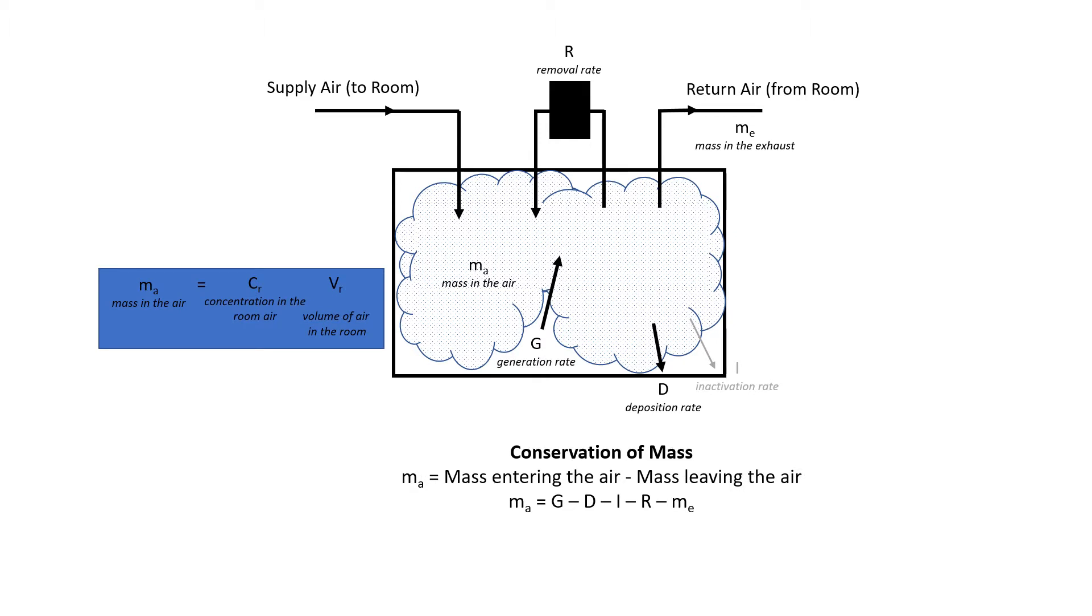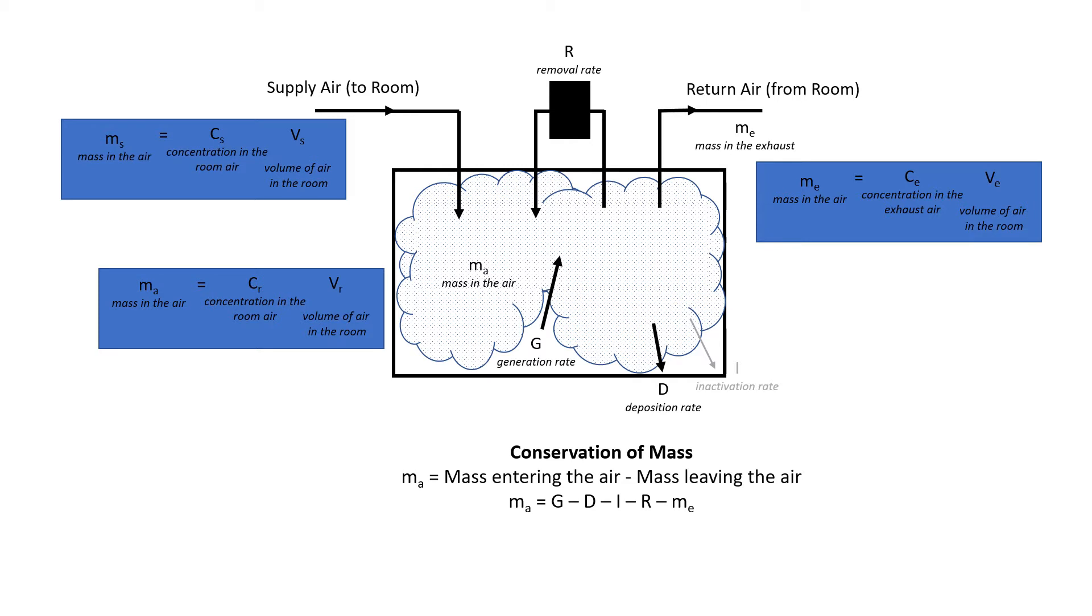We usually express these not in terms of the actual number of particles or the actual mass of particles in the room. We usually express it in a concentration. So it's going to be particles per meter cubed or micrograms per meter cubed or something like that. And so once we express them in terms of concentrations, we do that for the air flows as well, for the exhaust air and the supply air. That makes each component of this easy to express in terms of a volume or a volume flow and a concentration.